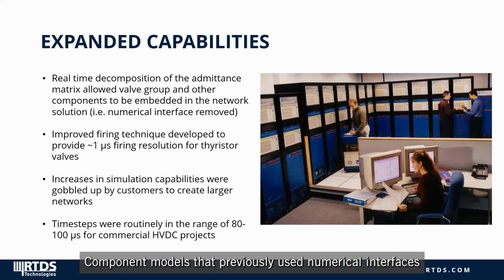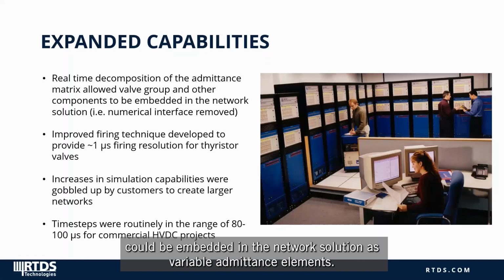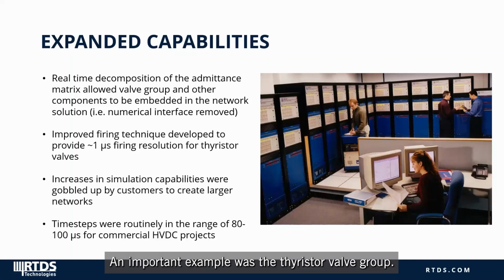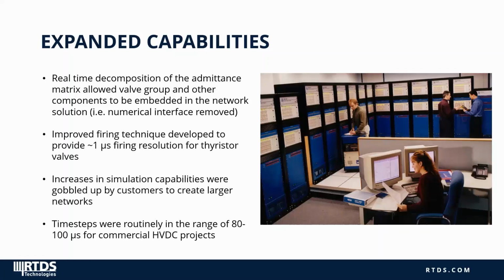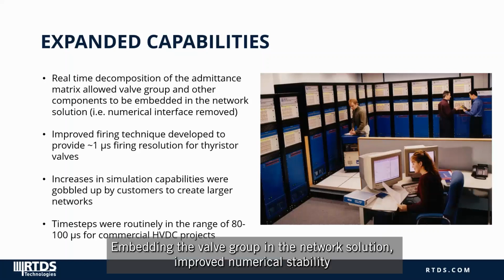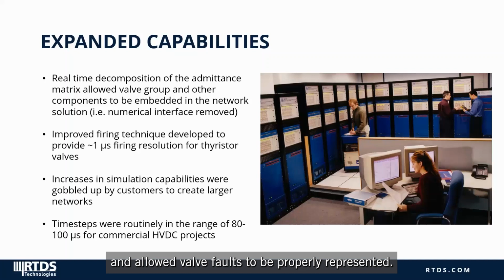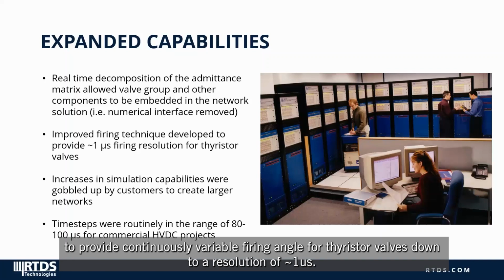Component models that previously used numerical interfaces could be embedded in the network solution as variable admittance elements. An important example was the thyristor valve group. Embedding the valve group in the network solution improved numerical stability and allowed valve faults to be properly represented. A new technique called improved firing was also developed to provide continuously variable firing angle for thyristor valves, down to a resolution of 1 microsecond.